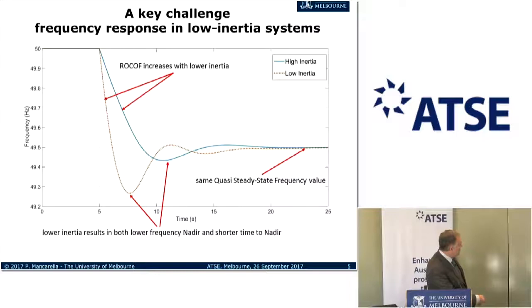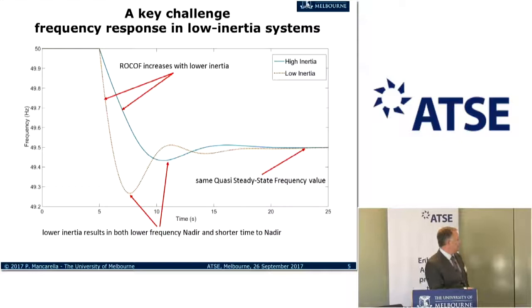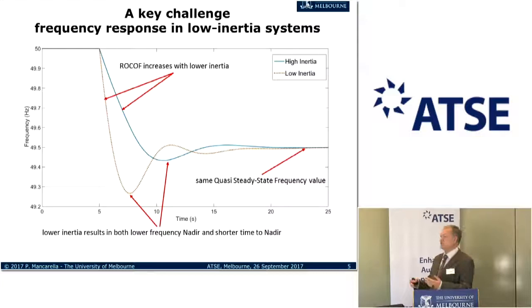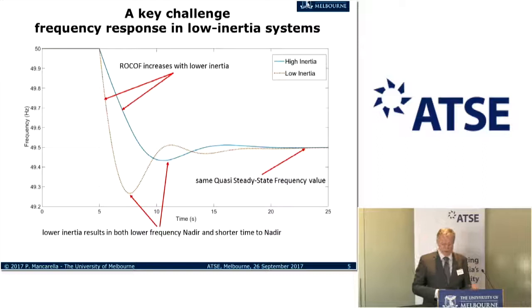We lose what's called ROCOF, rate of change of frequency. It's going to be much steeper if we have less inertia, and with less inertia we're going to go deeper—and that depth point is called the nadir point, the point where you have an imbalance again in the system, but it's the lowest point in your frequency.